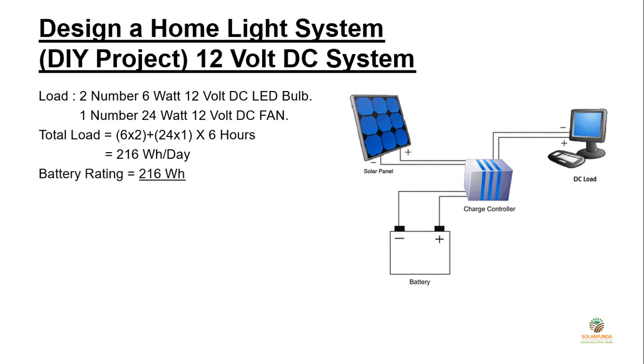Next, I will calculate battery rating by dividing total load by battery voltage, depth of discharge, and efficiency of battery. As an answer, 24 ampere hour 12 volt battery is required for my system.